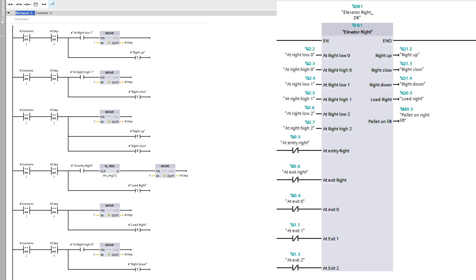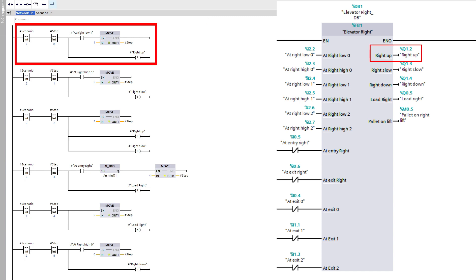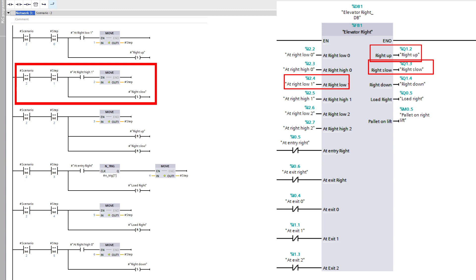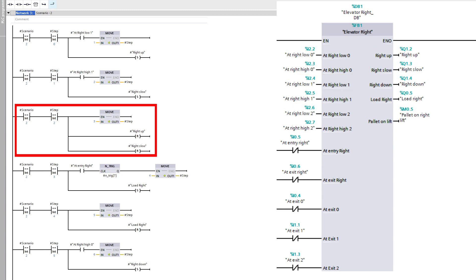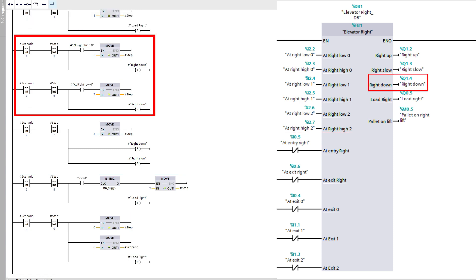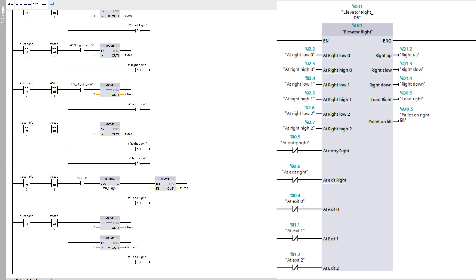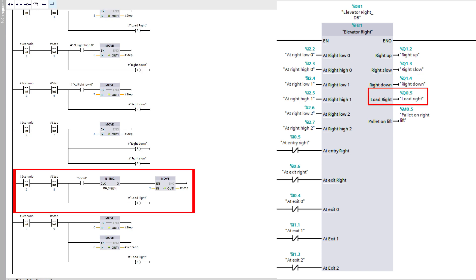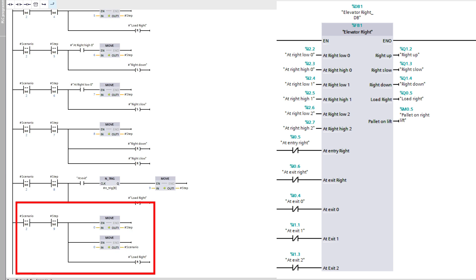If scenario 2 sets active, it will start a sequence similarly to the left elevator function block. First it will go up towards level 1, and at the lower sensor it will slow down and then stop at the higher sensor. Next it will load the pallet onto the elevator. Then the lift will go down to level 0 — same as going up, it will slow down at the first sensor then stop at the second sensor. The last step is to unload the pallet until it passes the exit sensor, then give the value 0 to the step sequence and scenario to reset them both.